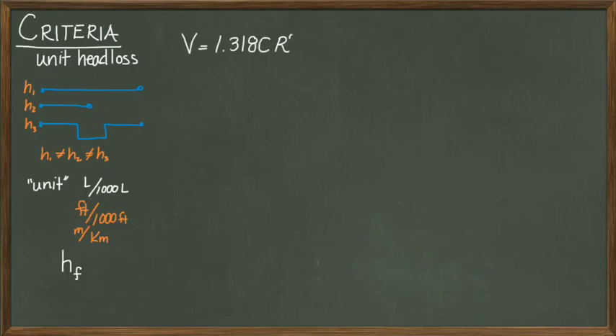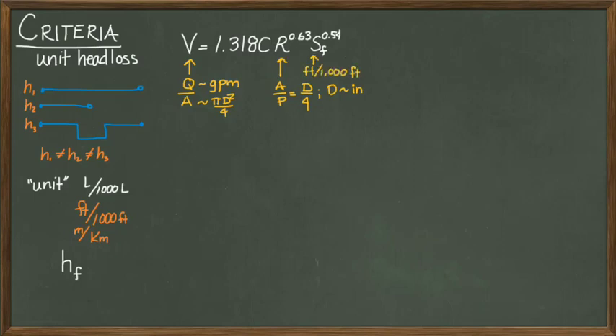Starting with the original Hazen-Williams equation, we can substitute in continuity, then convert the units of Q to GPM. We set area and hydraulic radius in terms of the diameter and convert the diameter into inches. Then insert feet per 1,000 feet for the friction slope.